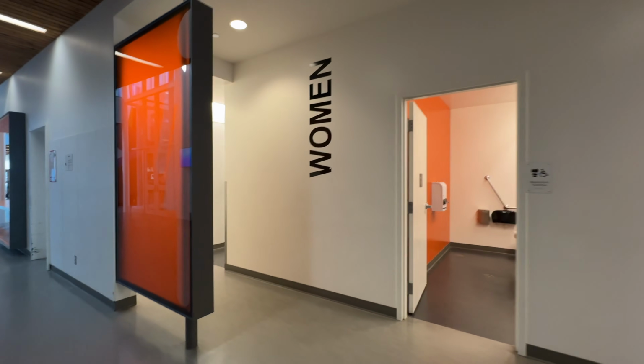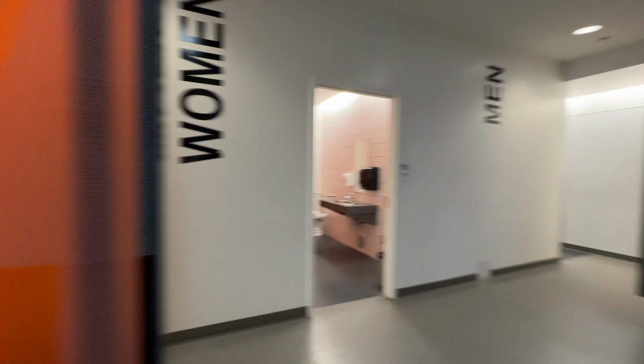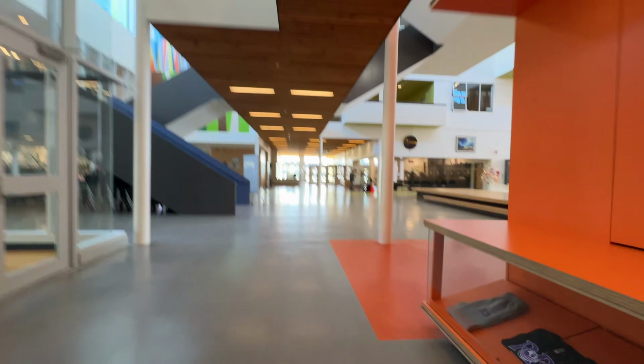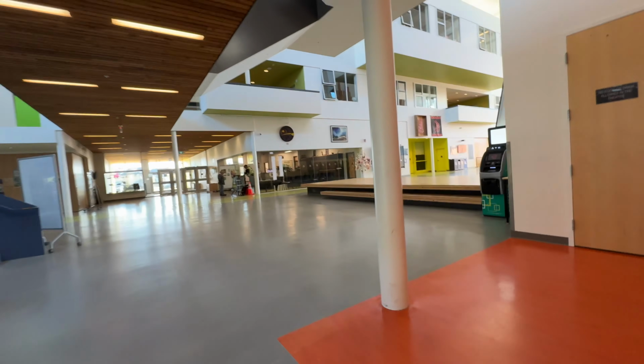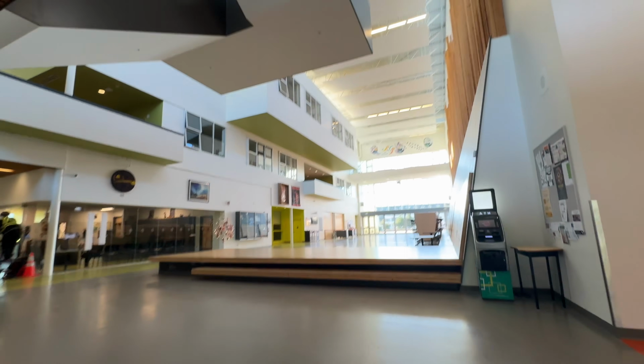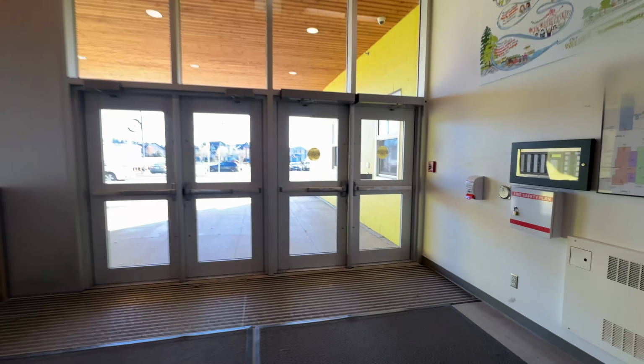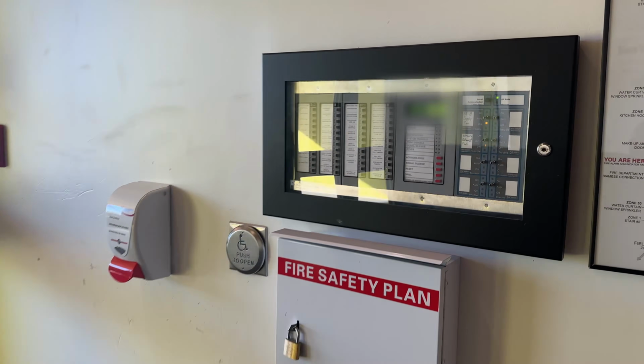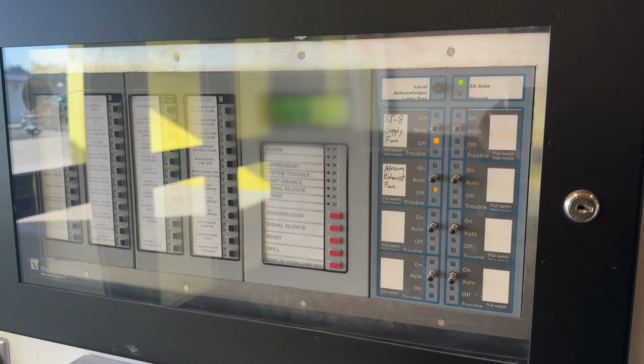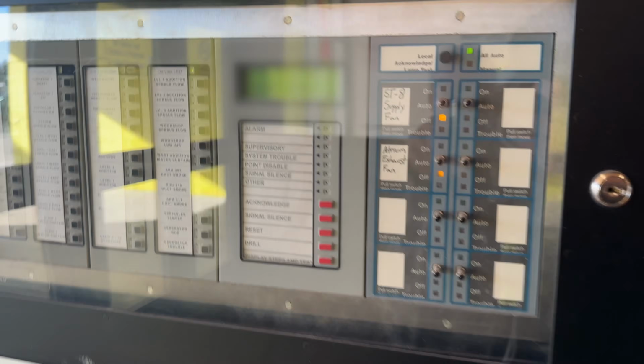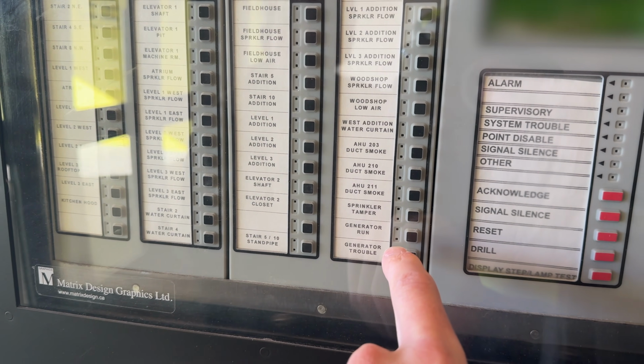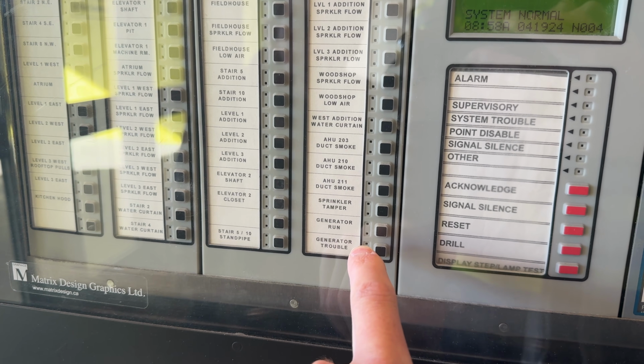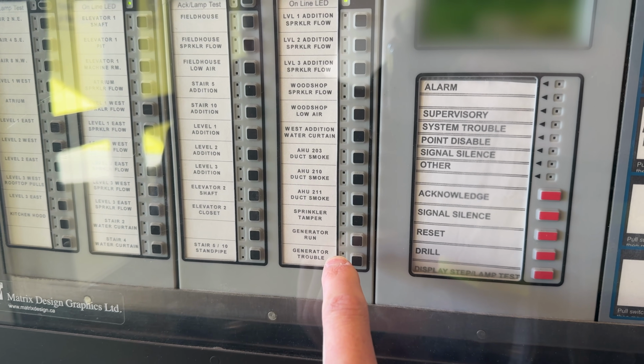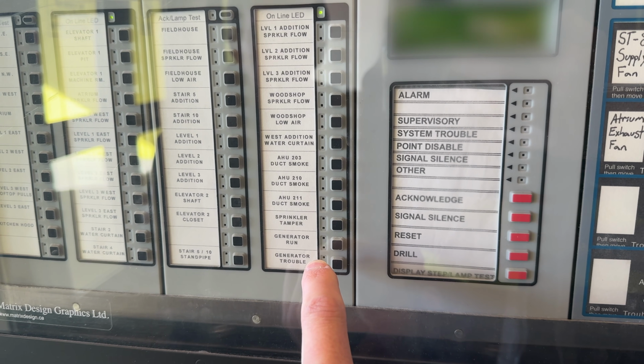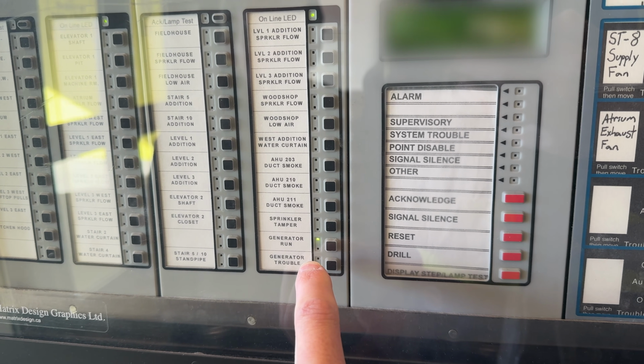Now these bathroom lights are also all generator power. So the last few times we've done this test here, the fire alarm hasn't gotten the generator supervisory, which it should be, for whatever reason. Okay, so now it is getting it, but it should be actually audible. So something's been changed here. So it is recognizing that the generator is running.